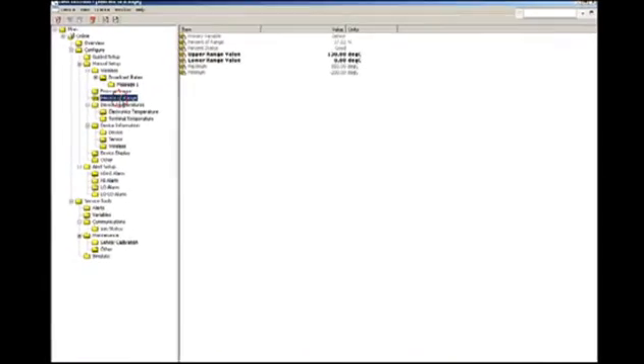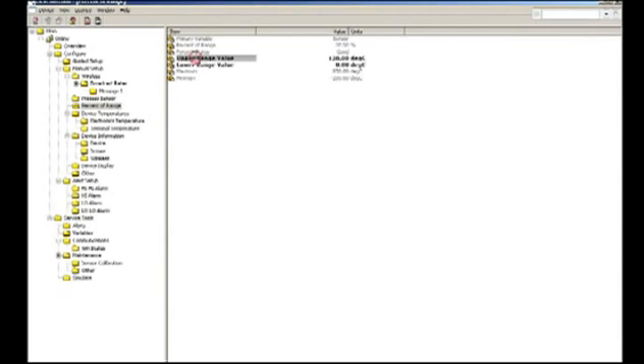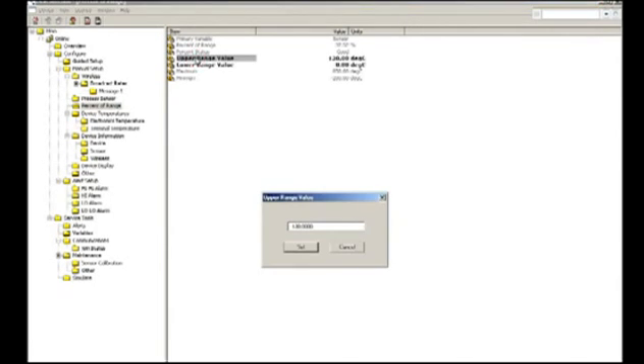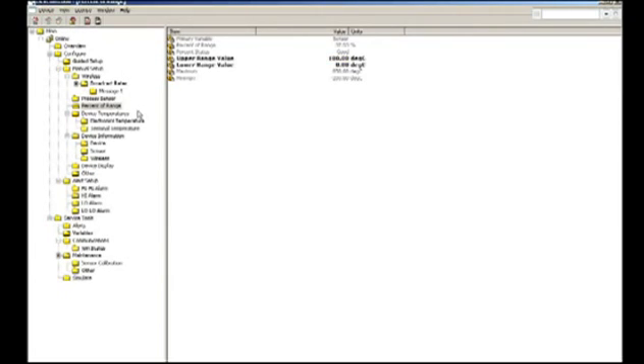On the right side of the computer screen we see the variables. Anything that is in bold can be edited. Anything in gray is read-only and can't be edited. Let's go ahead and double-click on the upper range value of the transmitter in order to edit it. After editing the variable, it becomes shaded in yellow, which means the variable has been edited but not yet committed to the device. After clicking on the send icon, the yellow shading goes away and the variable has been changed in the device. It's that simple.